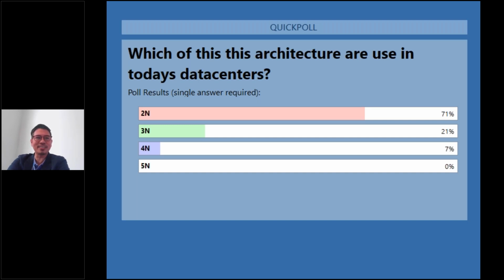Just a recap, as you can see here, we have the 2N. If we have a 1.2 megawatt load, 2N means you need to double it, so you have 2 units of 1.2 megawatts, a total power installation of 2.4. When you have this, it's not only your UPS, your battery should also be 2.4 megawatt, so you have a utilization factor.